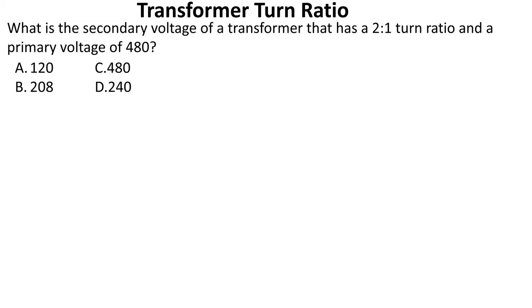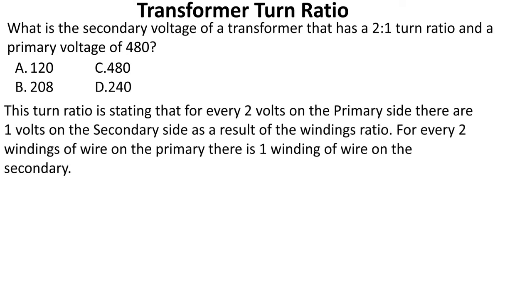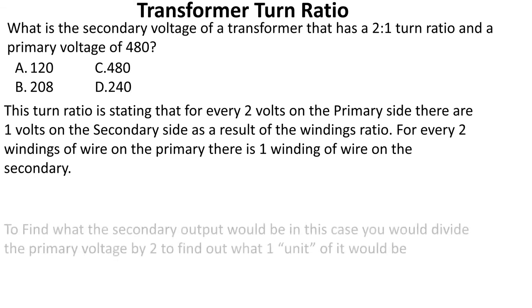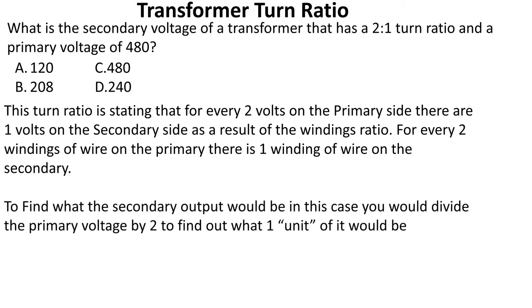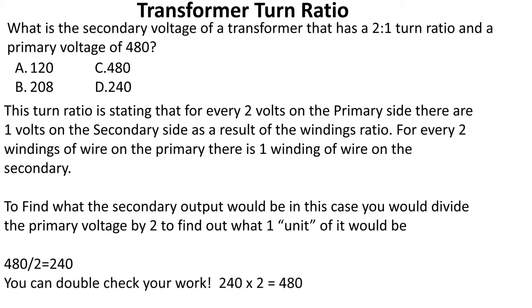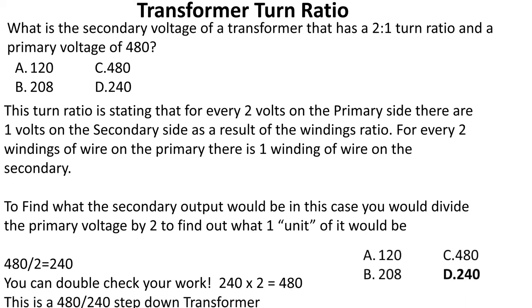What is the secondary voltage of a transformer that has a two-to-one turn ratio and a primary voltage of 480? This turn ratio states that for every two volts on the primary, there is one volt on the secondary. For every two windings on the primary, there is one winding on the secondary. Divide 480 by two to get 240. Double-check: 240 times two brings us back to 480. This is a 480-to-240 step-down transformer. We select D.